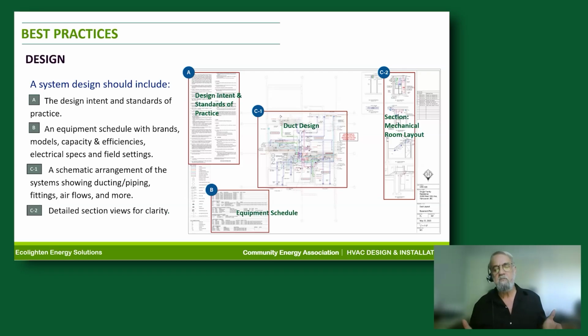And this is what we say: design should include the design intent and standards of practice. It's one thing to beautifully lay out the ducting and the hydronic piping and all that, but if it's done with a very poor standard of practice, it's not going to mean anything. The standard of practice should be in the design intent, and the design should include that. Of course, equipment schedules with brands, models, capacities, efficiencies, electrical specs, and field settings should be in the design. That's what we think.